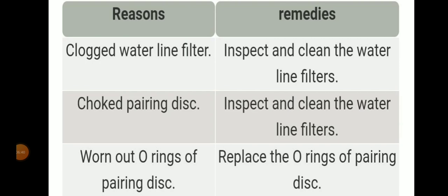A reason means clogged water line filter. Inspect and clean the water line filter. Choked pairing disc: inspect and clean it also. If the O-rings of the pairing disc have been worn out, replace the O-rings of the pairing disc.